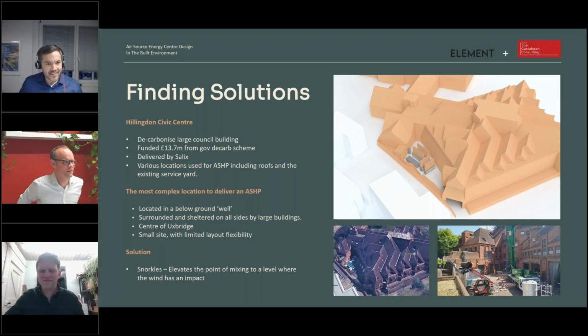I'll just pick up on this just to mention that that's the air dispersion, which of course is one of three core challenges. So here, of course, spatially, you can see how tight that is, and the closer we put these units to each other and the larger they are, this is driven by the capacity requirements of what is a very, very sizable building. This building is also listed, which means it has heritage protections, and that was a particular challenge.